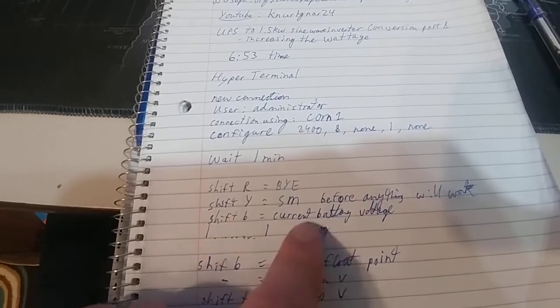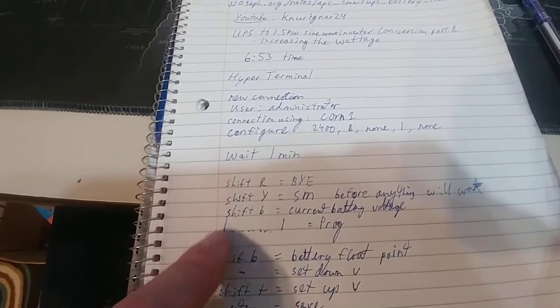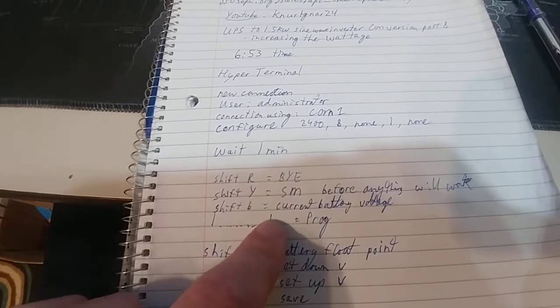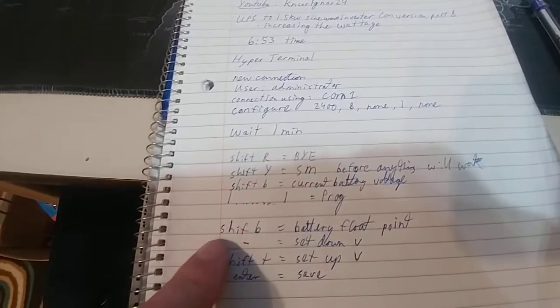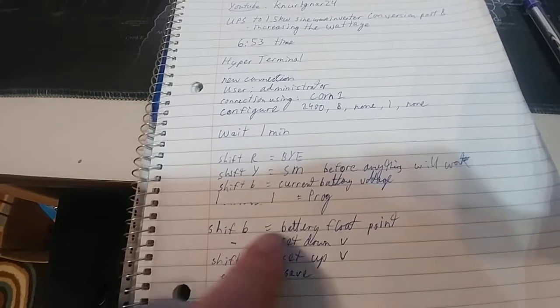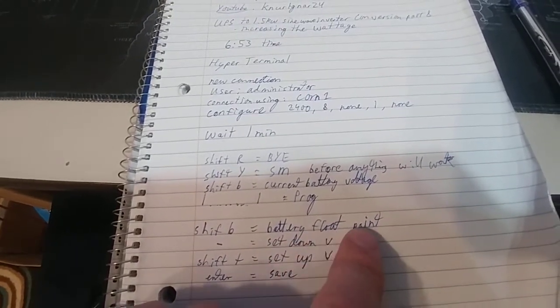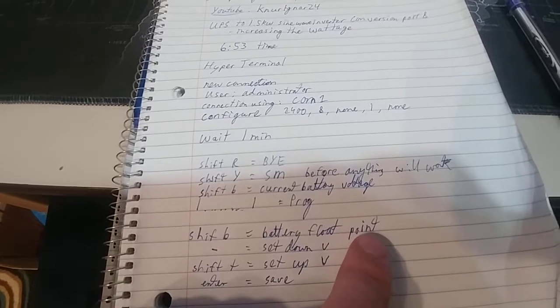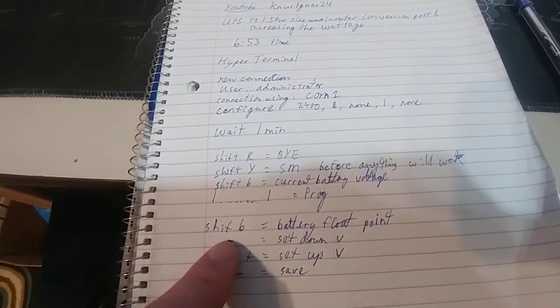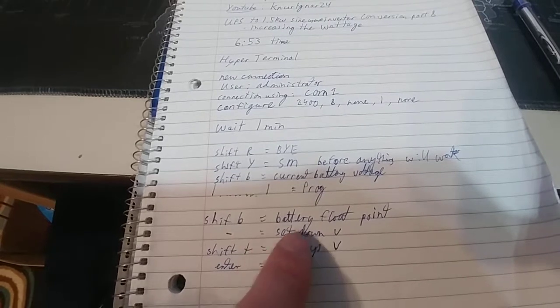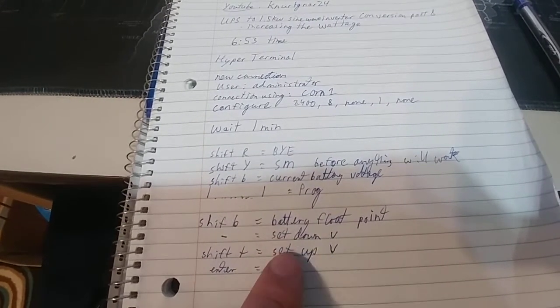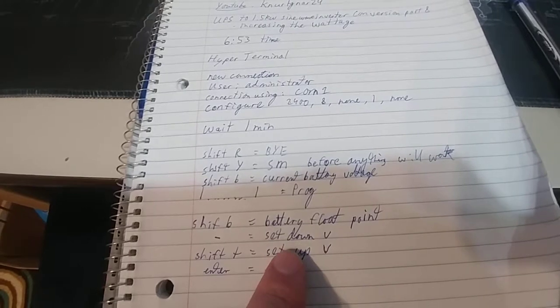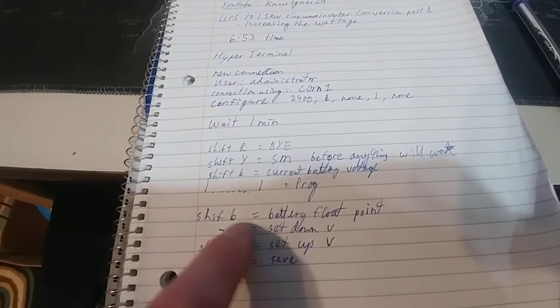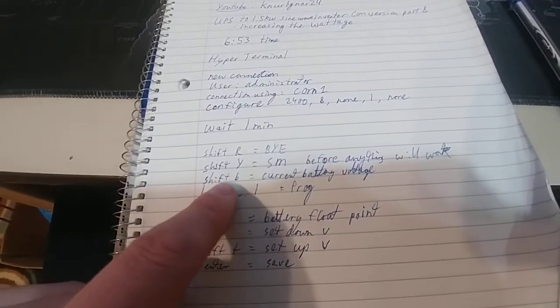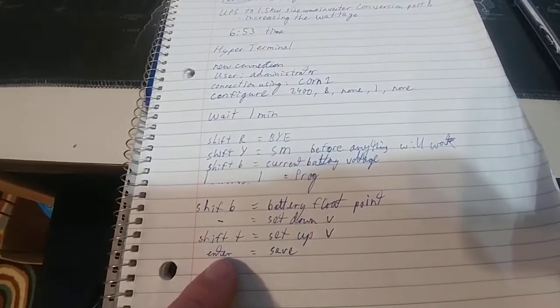Press Shift B and that'll tell you what the current battery voltage is. Press 1, wait a little bit, then press 1 again, it'll say program. Then you hit Shift B, and it'll tell you the battery float point. So that's the max voltage it'll bring it up to. And you use the minus and the Shift plus in order to bring the value up or down. It'll spit back a hexadecimal value, but you don't actually need to worry about it. You just have to keep changing it and pressing enter and then checking again by pressing Shift B, in order to figure it out, and then you hit enter to save your final voltage.